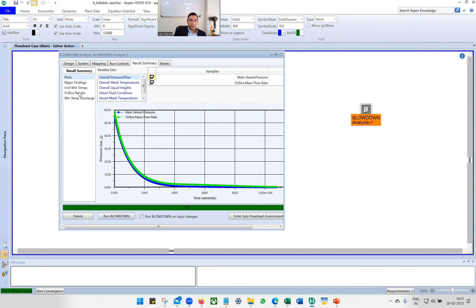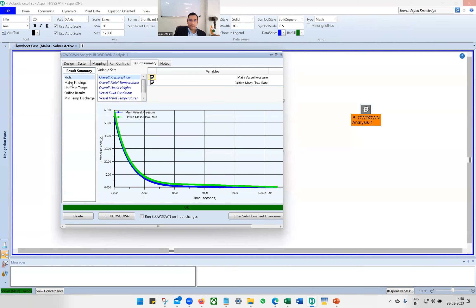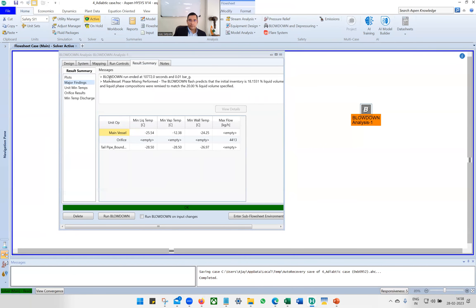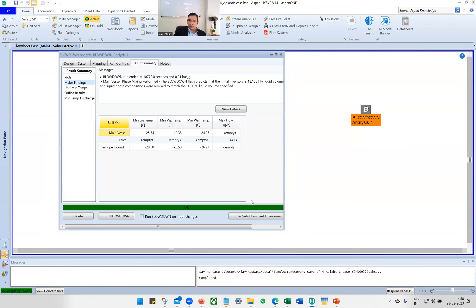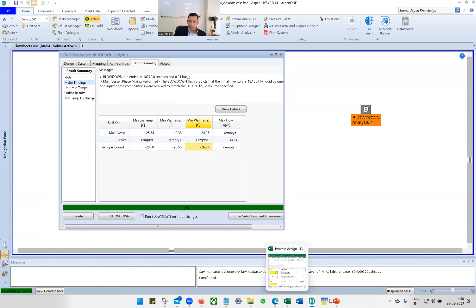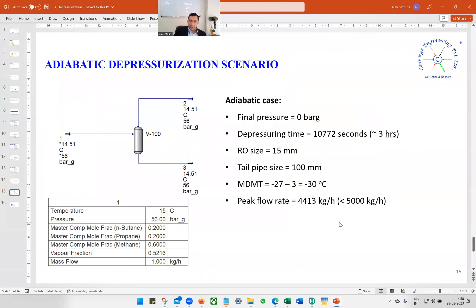After running the blowdown and going to Result Summary and Major Findings: the blowdown run ended at 10,000 seconds with a final pressure of 0.01 bar gauge. Maximum flow rate is 4413 kg/hr. Minimum wall temperature is minus 27°C, so MDMT would be minus 27 minus 3 equals minus 30°C.